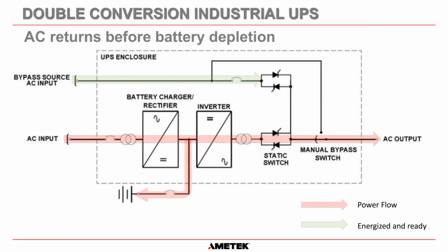Okay. So let's say the AC returns before the battery completely discharges or before it completely depletes. All that happens is the sensing inside the battery charger rectifier sees, okay, I now have my 480 volt AC back in again. So there is no switching involved. There is no interaction with any plant staff at this point here. The battery charger just says, okay, I've got my power back, and it switches itself back on again, and it will start to recharge the batteries and go back to feeding the power needed for the inverter. Once again, no switching involved whatsoever.